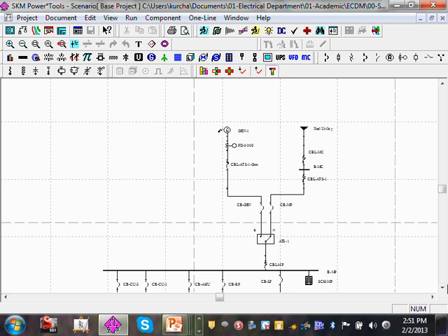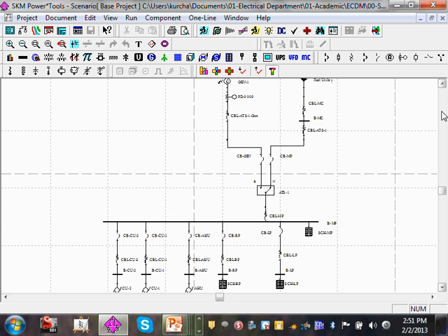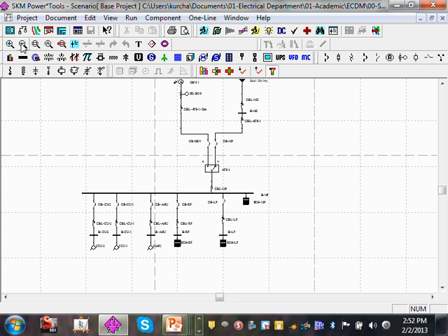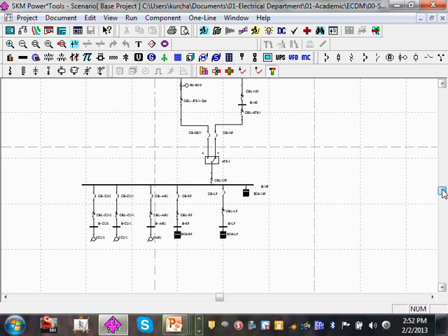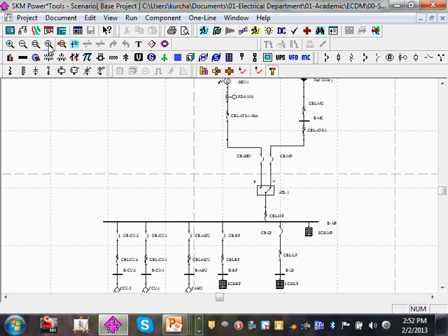So let me just walk you guys through this system, a very little system here. Let me zoom in here. Okay, or maybe zoom out and see what we can. I don't know how much you guys can see, this is software that we do short circuit analysis on. Starting right at the top here is Xcel Energy, and it could be Minnesota Power. We pick on Xcel because we're in the cities. Coming here, the transformer that I showed you when we were doing that bonding and grounding, we grab our cables directly here into what happened to be a meter, we're simulating the utility here.